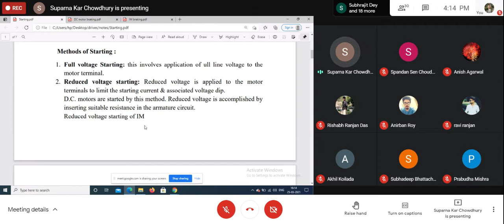Now, reduced voltage starting, say for DC motor, when we apply a starter, if you remember a 4-point or 3-point starter, that is basically a reduced voltage starting. That is, we insert a resistance in series with the armature, and part of the voltage is dropped in that resistance, so a smaller voltage is applied across the armature. When we go for an automatic starter, the same principle is there. That is, the resistance is not cut off manually, but it is cut off in stages.